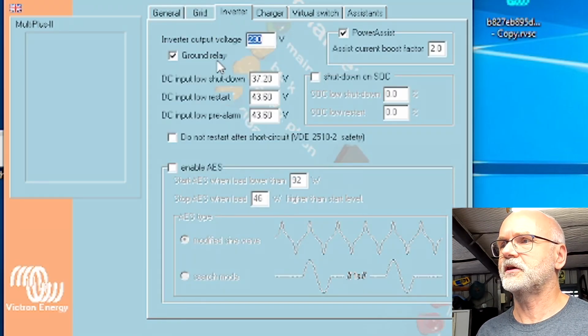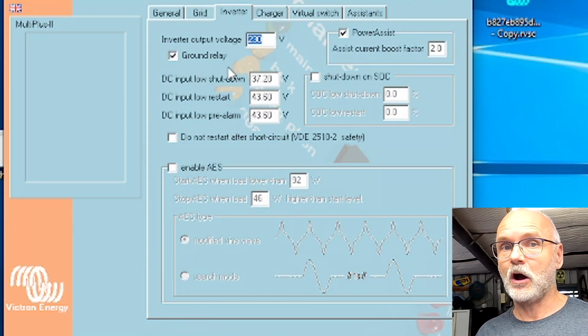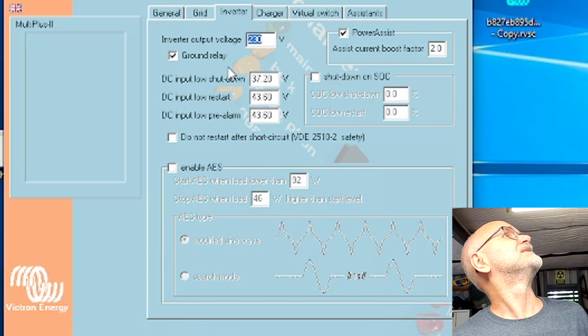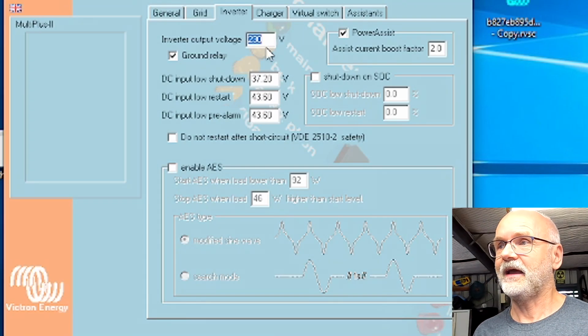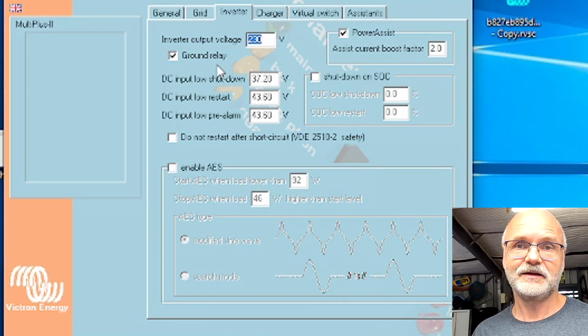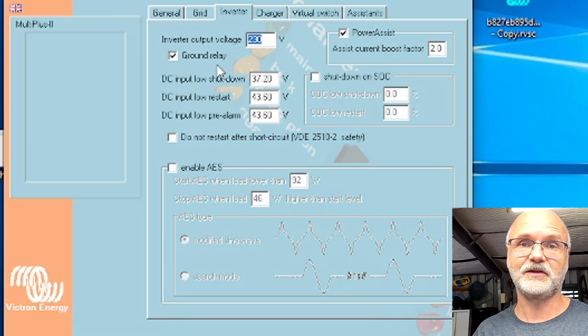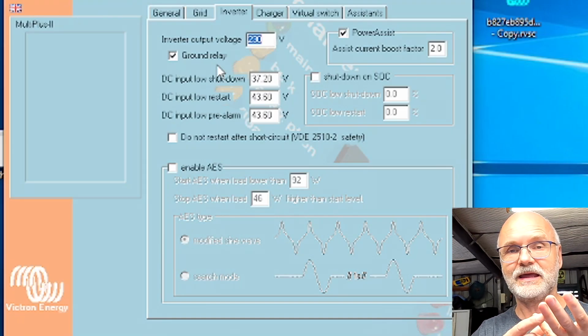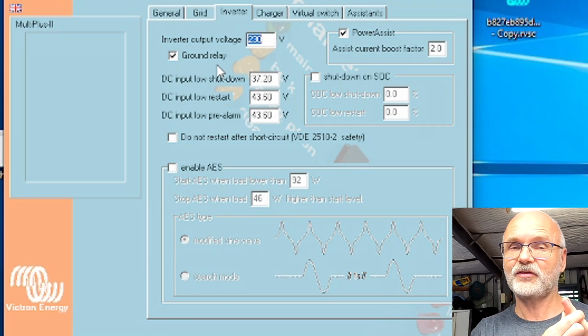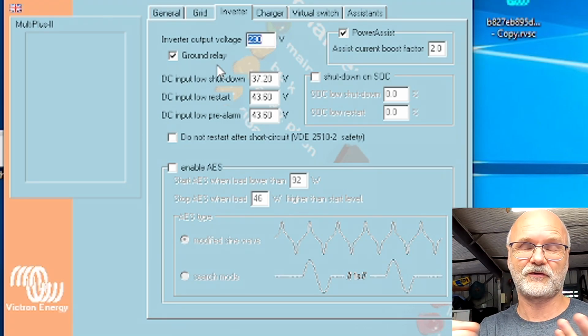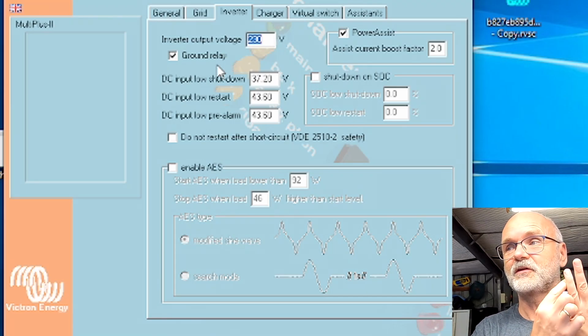We go into the inverter settings, and here we can set the output voltage, as well as the ground relay. The Multiplus has a built-in MEN link, meaning the neutral and the ground are internally bonded with a relay. As soon as the Multiplus connects to an external source, it will open this contact.